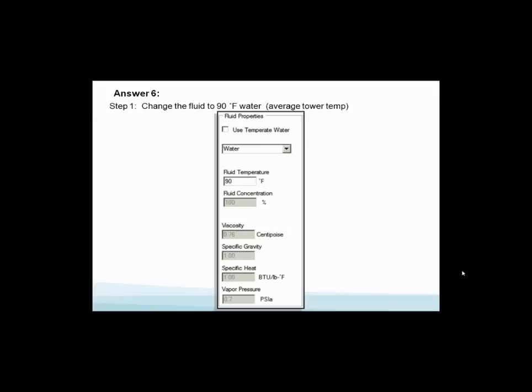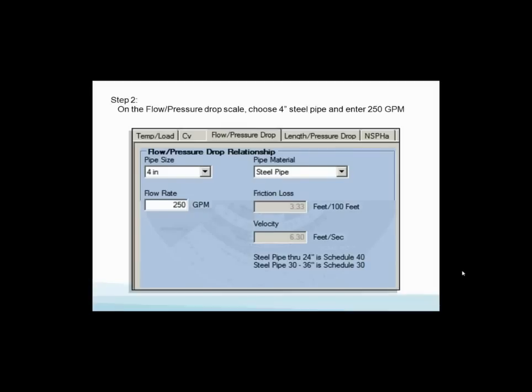Let's take this information. Let's go to our system sizer. First thing we're going to do is correct that water temperature. We said 85 to 95, so we go to fluid property. Let's correct it to the average water temperature - 85 to 95, average is 90 degrees. We've got water, fluid temperature is 90. Let's go pick a pipe. We've already done that - we've been to the flow pressure drop chart to come up with 4-inch pipe at 250 GPM using steel pipe. You see the pressure drop is 3.33 feet per 100 feet of pipe. The velocity is 6.3 feet per second, and this is based on Schedule 40 steel pipe.